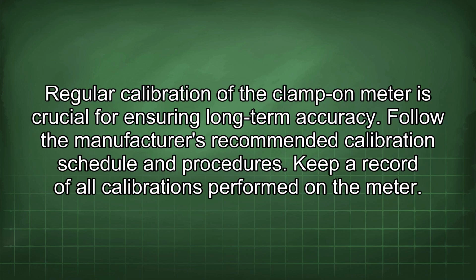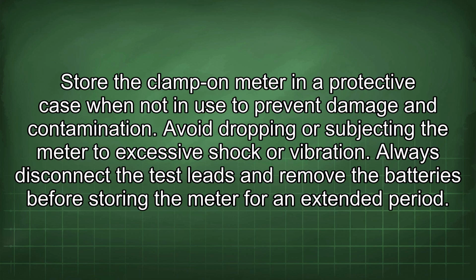Regular calibration of the clamp-on meter is crucial for ensuring long-term accuracy. Follow the manufacturer's recommended calibration schedule and procedures. Keep a record of all calibrations performed on the meter. Store the clamp-on meter in a protective case when not in use to prevent damage and contamination. Avoid dropping or subjecting the meter to excessive shock or vibration. Always disconnect the test leads and remove the batteries before storing the meter for an extended period.